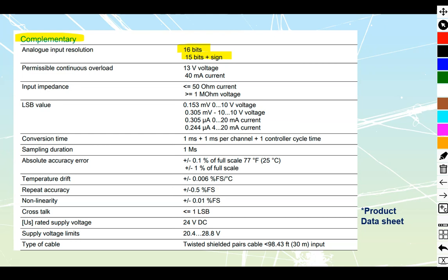This is good because a lot of your smaller PLCs, the onboard ones you're going to have, are usually going to be fewer than 16 bits. So if you need to have a really precise signal, you want to go out to something that gives you maximum resolution so you can see the smallest changes in your voltage coming in. 16 bits is a great range to have, far beyond what most of you will ever need for accuracy in most industries you're working in.